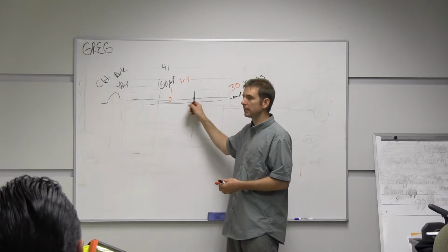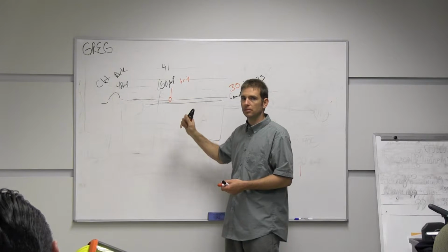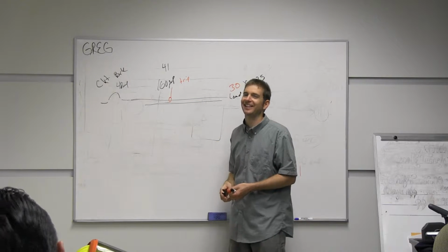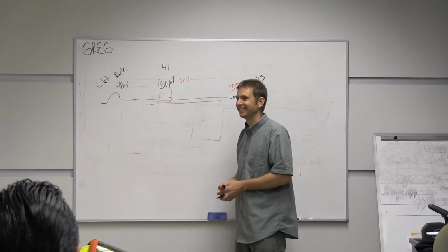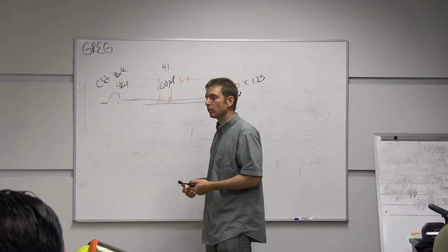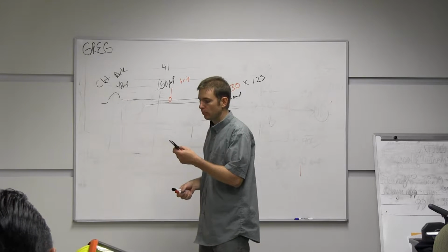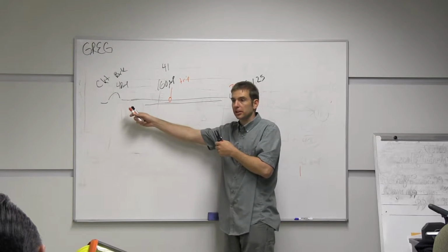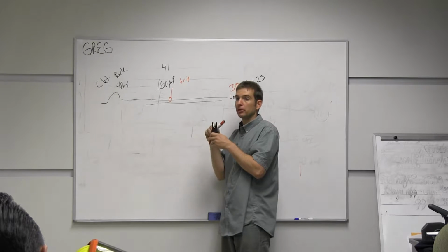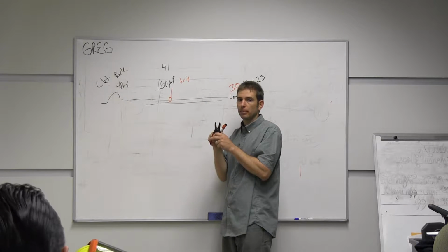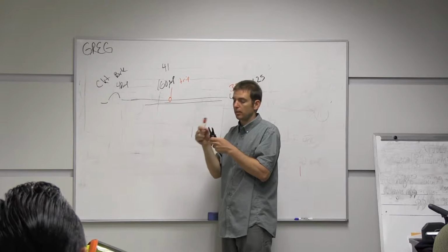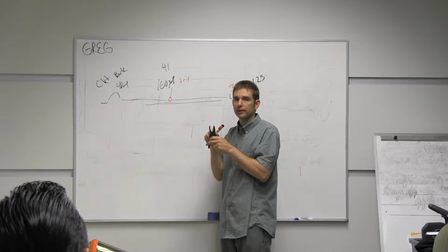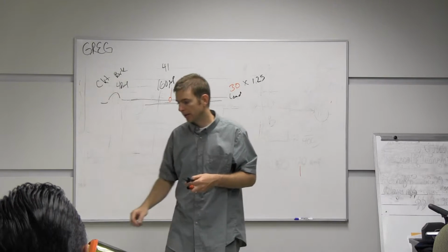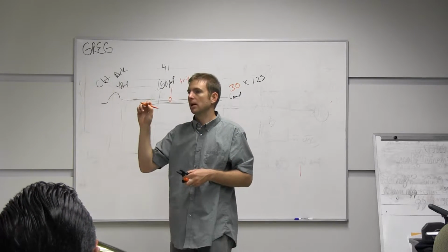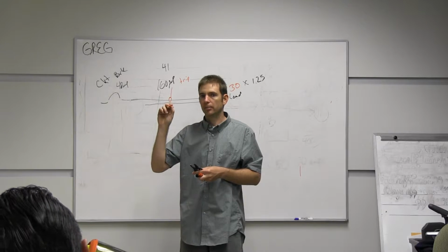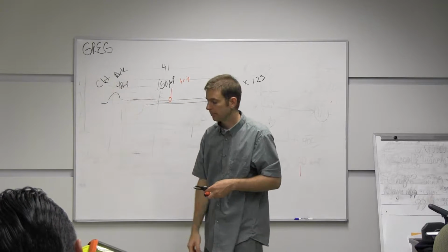I cut these both at the same time with the same tool. You've never done that, huh? You weld your... I've done that. Well, quite possibly you're going to weld it. I'm going to cut this. Hopefully my breaker's going to trip, but I'm going to create a small arc blast. It's going to destroy my tool. I'm going to weld, or probably leave some slag on here. I'm going to burn a hole in this. The hole is probably going to be, again, about the size of 10 gauge wire, about the size of the lead on the end of a colored pencil.